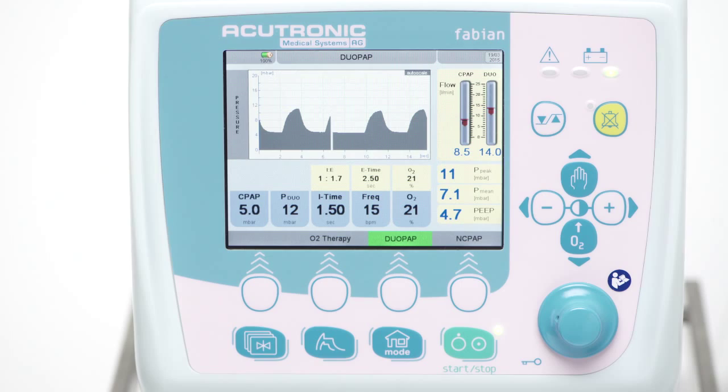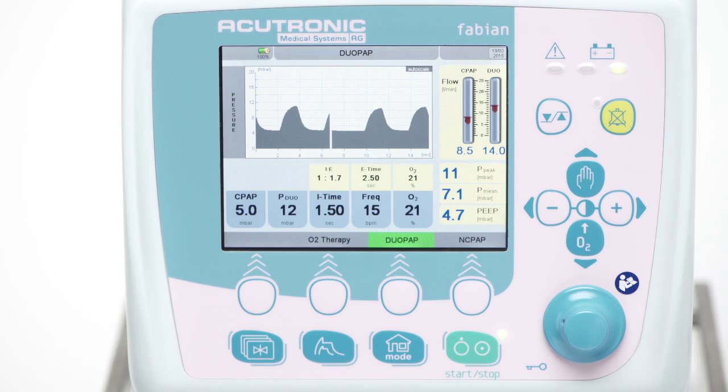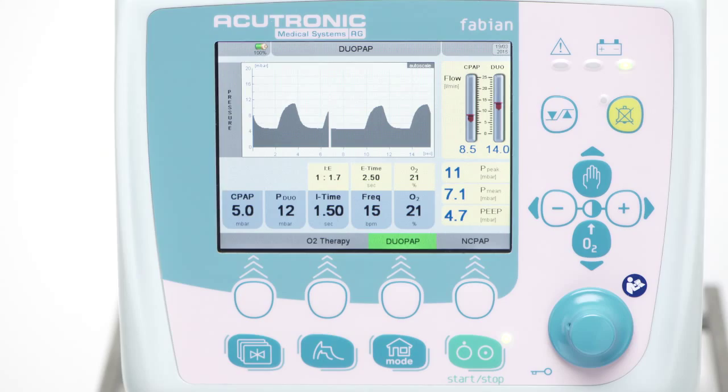In addition to the NC-PAP mode, the DUO-PAP modality offers non-invasive ventilation on two different pressure levels, and therefore may be beneficial to increase the ETCO2 washout, or act as a mode with a fixed amount of breaths to stimulate babies with increased apnea events.